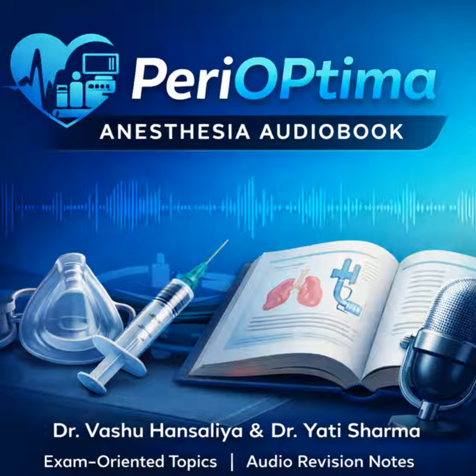Coaxial just means along the same axis. The fresh gas is delivered through a narrow, flexible inner tube, while the exhaled gases return via the wide outer tube that surrounds it. The patient connector is where that inner tube terminates, which effectively places the FGI right at the patient's airway, the critical arrangement for Mapleson D efficiency.